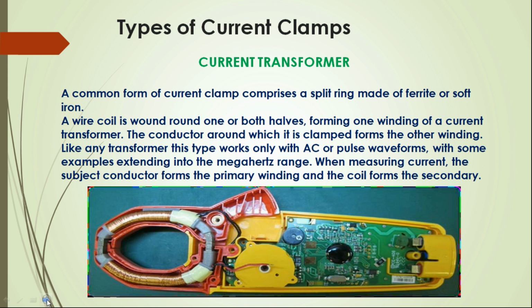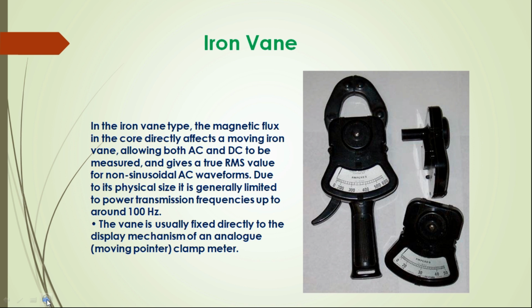Next is iron vane. In the iron vane type, the magnetic flux in the core directly affects a moving iron vane, allowing both AC and DC to be measured and giving a true RMS value from non-sinusoidal AC waveforms. Due to its physical size, it is generally limited to power transmission frequencies up to around 100 Hz. The vane is usually fixed directly to the display mechanism of an analog clamp meter. Here is the picture.